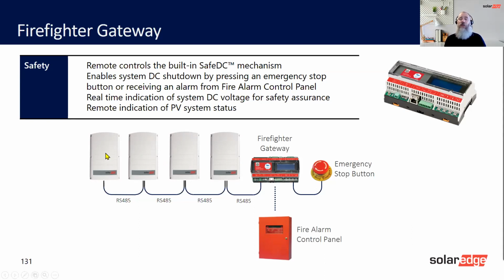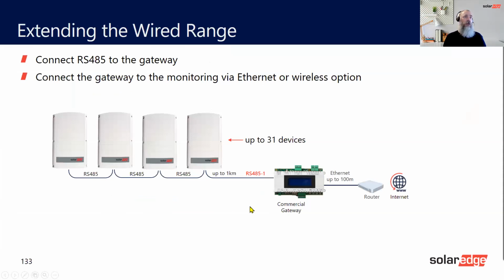The inverters have SafeDC. The inverters will do all the SafeDC just as they are anyway. This is just a link to the fire alarm panel. Great device. So the gateway itself, let's have a look. Again, it supports up to 31 devices. This is the leader. These are the followers. RS485 cable gives you a kilometer. Cat 5, Cat 6 gives you 100 meters.